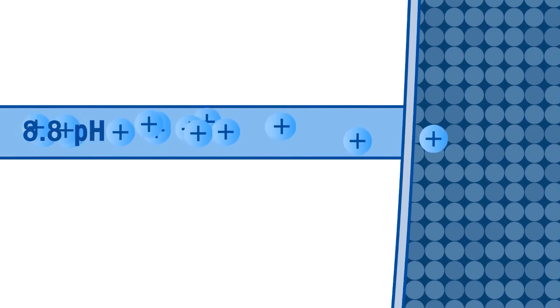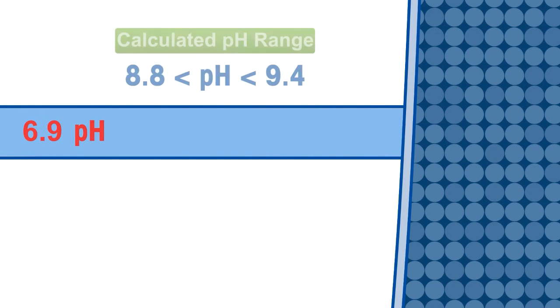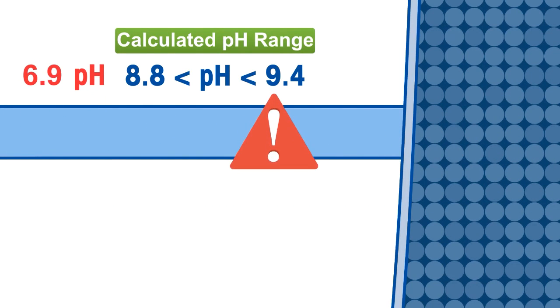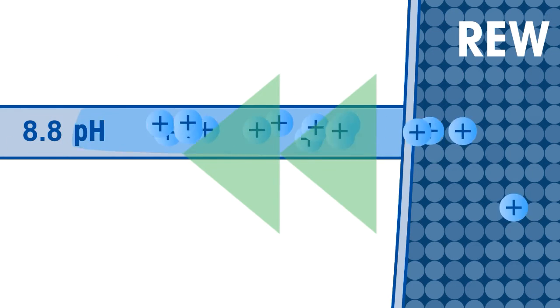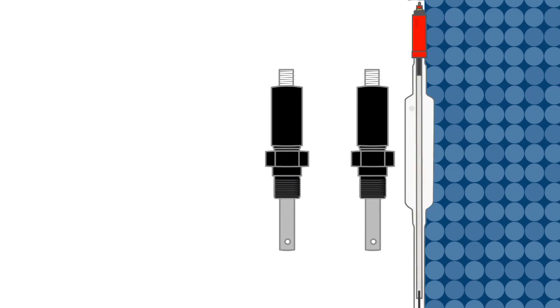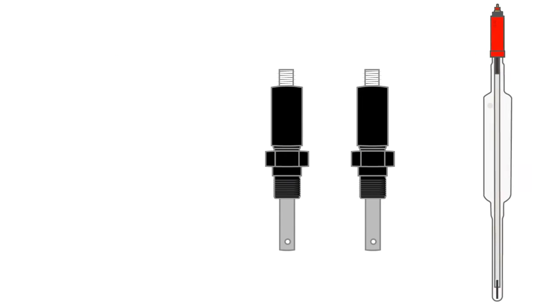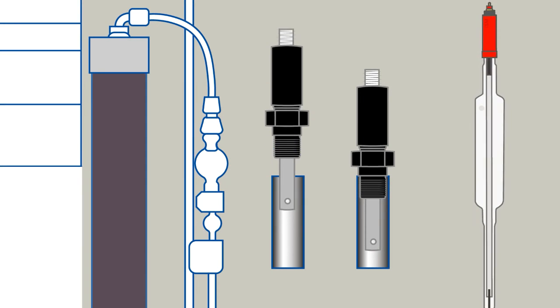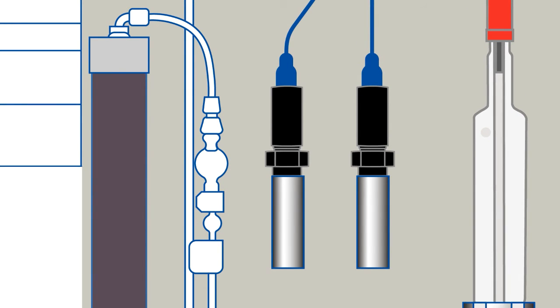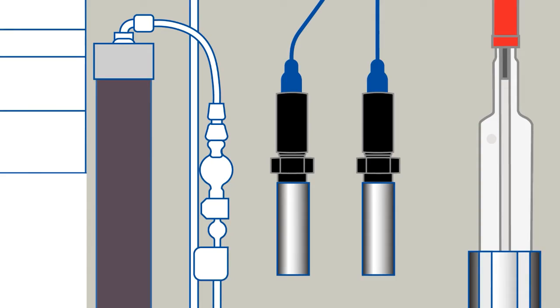This is outside the ideal range for using calculated pH and would generate errors. Thus, to avoid contamination, it is recommended that both traditional pH measurement and calculated pH based on conductivity be used for optimal pH control.